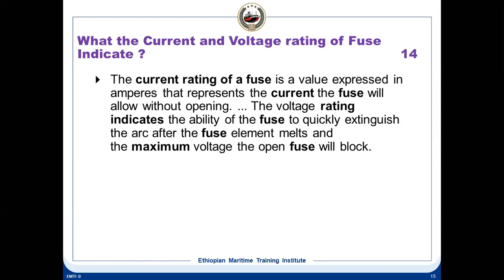With a higher voltage rating, the electrode gap is larger, so there is no chance of the arc reigniting. When you use a low voltage fuse, the gap is smaller, so there can be another arc when the current is interrupted. Okay, so this is the difference between current and voltage rating of a fuse.